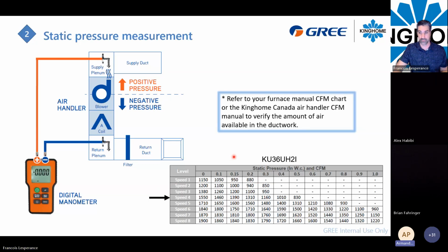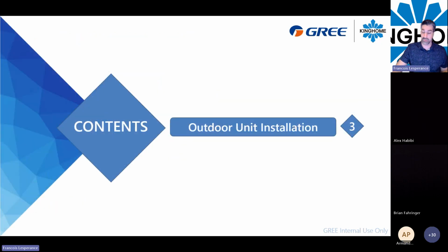And on this air handler, to change the blower speed, is it dip switches or just changing around wires off the board? It's dip switches. Perfect. So you just put the power off, change your dip switch, bring the power on, and retake the measurement again. Thank you very much. No problem, sir.